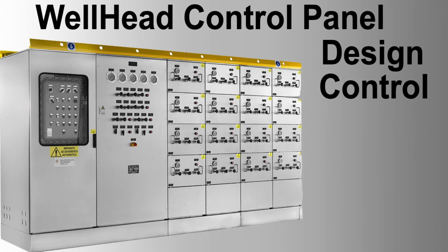Shutdowns function: automatically shut down the system to prevent damage or hazardous situations. Types of shutdowns: emergency shutdown (ESD) activates in response to critical failures or safety breaches. Process shutdown activates in response to process deviations beyond acceptable limits. Devices used: ESD valves close to isolate the well and prevent flow. The PLC or RTU executes shutdown logic and activates ESD valves. Sensors detect conditions that trigger shutdowns. Control via PLC or RTU.